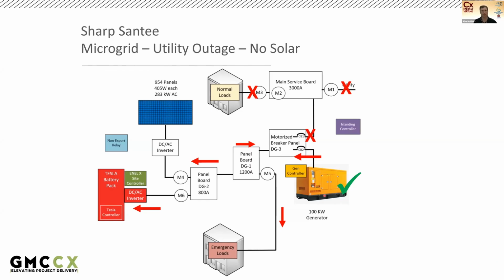Once the generator comes on, it supplies power to emergency loads, and it also charges the battery. It'll charge it up to about 60%, and then leave it there. That was also another thing that was field adjustable. So this happens until utility power is restored. Upon restoration, the islanding controller synchronoscope measures waveforms between the Tesla and utility and allows breaker CB1 to close after 5 minutes to verify synchronization. So similar to an ATS, it's looking at what's available on the emergency side and what's available on the normal side, and it will make that transition after 5 minutes.